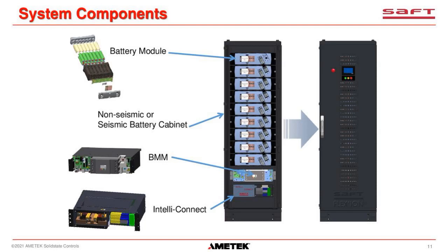Next, we have the BMM, which stands for Battery Management Module. Inside this module is a circuit breaker, power contactor, and a circuit board that collects measurements for all the modules inside the cabinet. The BMM prevents short circuits and overcurrents. It also has overheating protection and overcharge protection. And it also has charge protection after an over discharge. So for lithium-ion batteries of the LFP type, if you discharge the battery to 0%, it is not safe to ever recharge it and use again. So this BMM prevents that from ever happening.